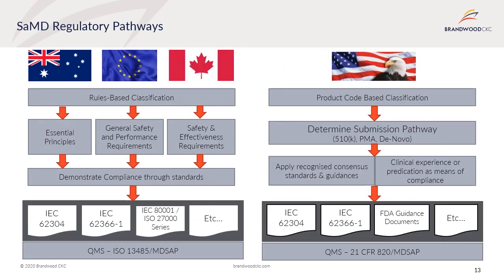Your product will be regulated in the same way as other medical devices of the same risk class. There are basically two frameworks: the GHTF approach adopted by Australia, Europe, and Canada, and the pre-market submission approach used in the US. For the GHTF approach, the medical device classification must first be determined based on a set of classification rules. The level of regulatory intervention is based on the class applied to the device. Each jurisdiction has a set of mandatory requirements concerning medical device safety, design, labelling, clinical evidence, and so on — in Australia these are the essential principles, in the EU the general safety and performance requirements, and in Canada the safety and effectiveness requirements.